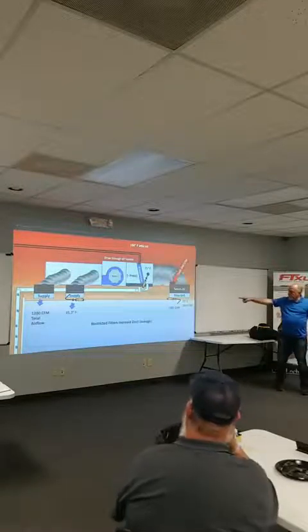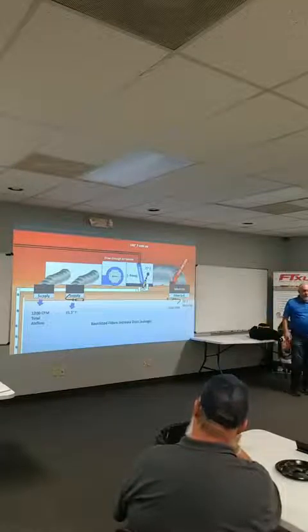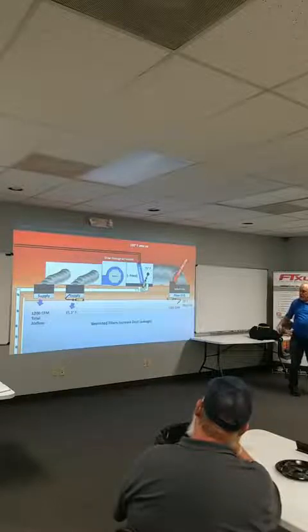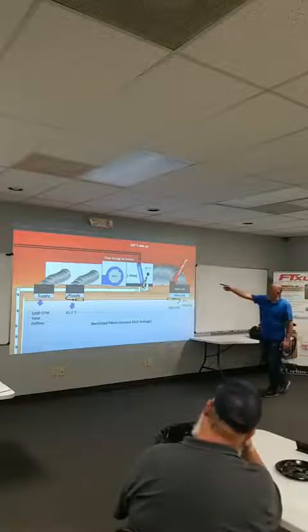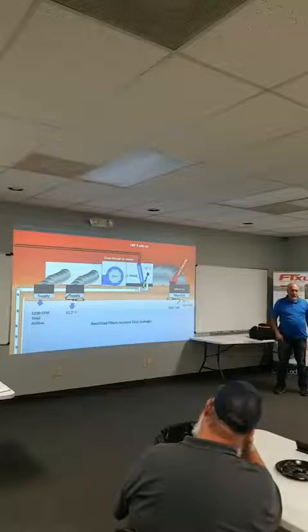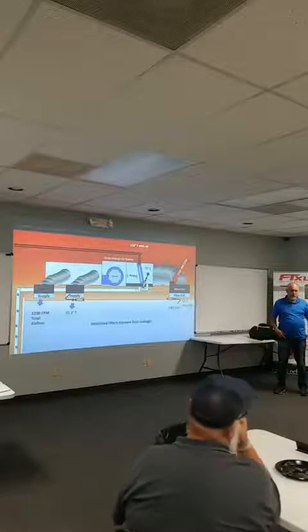Let me explain why. If I have 70-degree air going in there, right? That 70-degree air is the driver for my suction pressure, correct? On my machine. Everybody agree with that? So if I have 75-degree air going into the equipment, and this is what happens a lot of times. Guys, you go up, you put a probe up in the equipment, it'll be 75 degrees, and you adjust the blower down to get a 20-degree split, right? You adjust it down, you go, oh, the split's no good, I'm gonna get a 20-degree split off this thing.